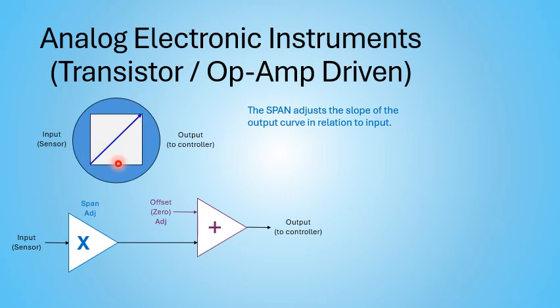So basically, what they had is a gain amplifier, which was basically our span adjust, the little S adjustment, and that would adjust the steepness of this blue line here. It would make it steeper or shallower, but it would change the slope. And then the signal would feed into another circuit where they would adjust the offset or the zero, the Z adjustment. And that would simply add some amount to the whole line or subtract it. It would move the whole line kind of in parallel up or down. Well, basically, with those two adjustments, you could adjust everything.